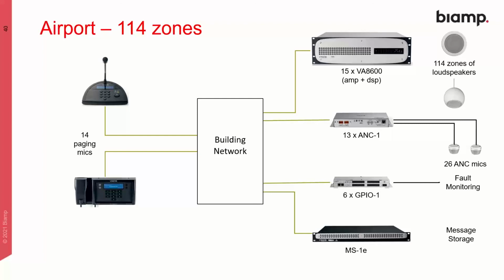So that's logic connections to and from the system to outside devices. And then an MS1E, which is a message storage device. So that is actually used for holding any of the messages, either temporarily or to be uploaded from the automatic announcement system. So in this case, it's a manufacturer called AviaVox, which uses an FTP flow of messages to the MS1E, and then the messages are played back after the upload. So hopefully that's useful for you to see that this is a real live application here.